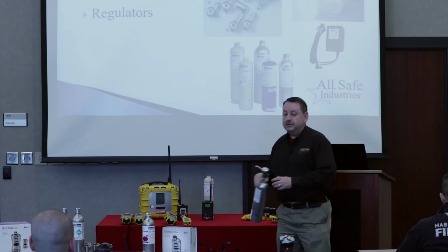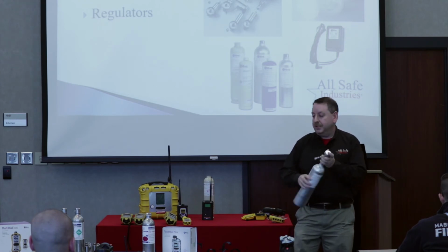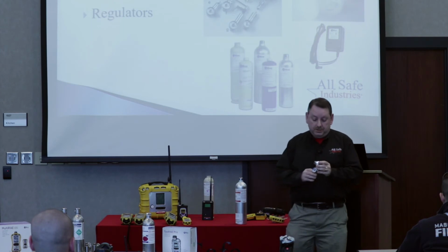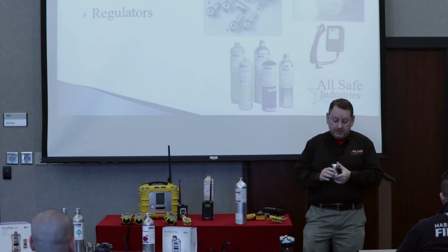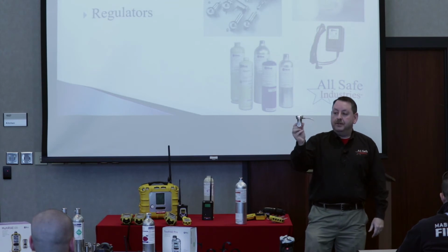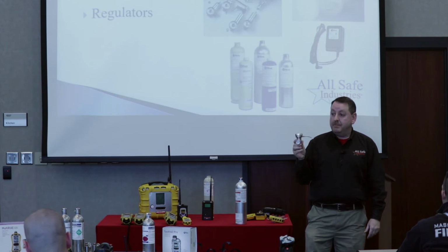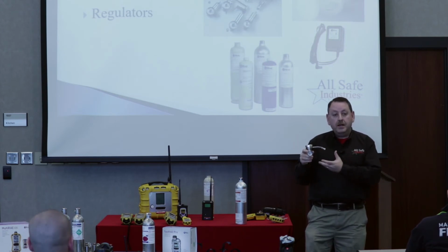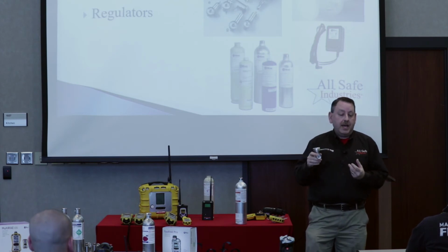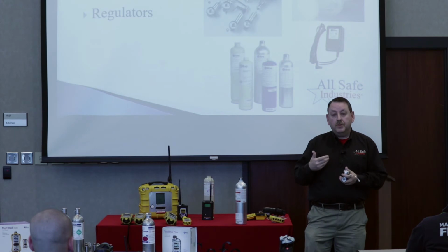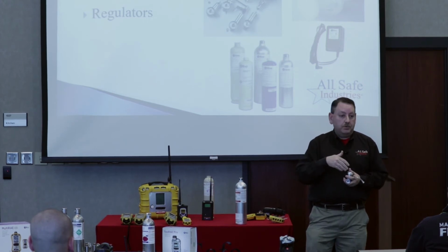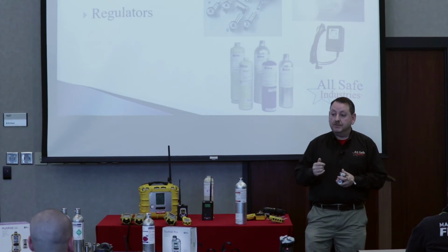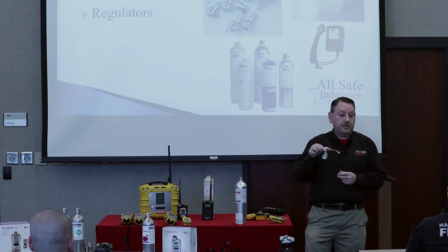And then the one I was showing on this cylinder, this one is called a demand flow regulator. And again, this is what you guys purchased. You needed the demand flow regulators to work with your calibration stations. But what's great about a demand flow regulator is it flows the gas at the exact rate that the pump in your meter demands it. So when you hook this up to a pumped instrument, the regulator will flow out the calibration gas. And I call it the perfect calibration because it's flowing gas to the instrument the same way it would pull gas out of a confined space and run the test on the atmosphere. So again, I call it the perfect calibration because it feeds the pump the exact amount of gas being demanded by the pump, and that's why we call it a demand flow regulator.